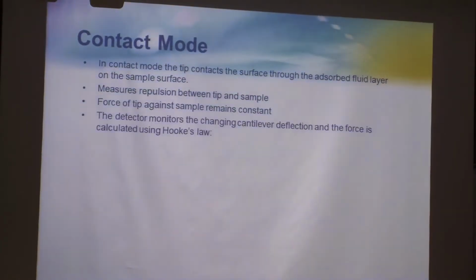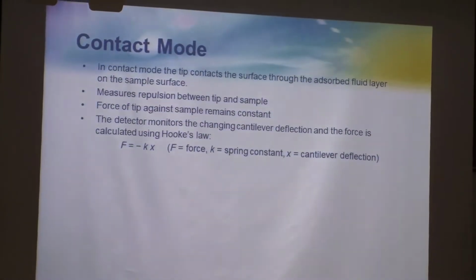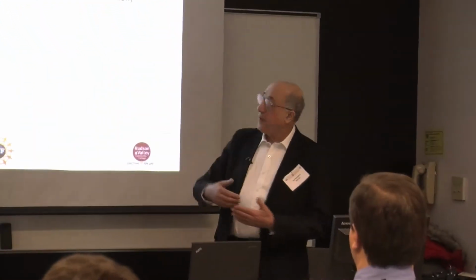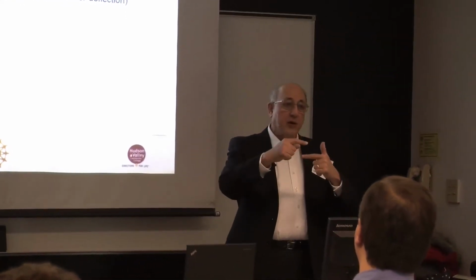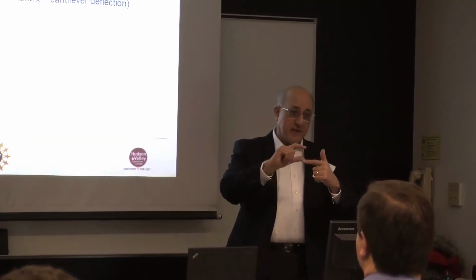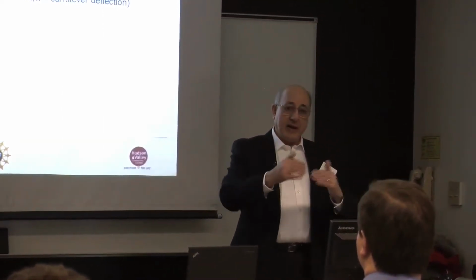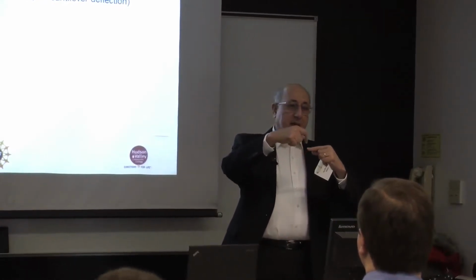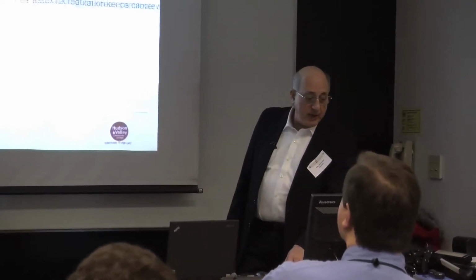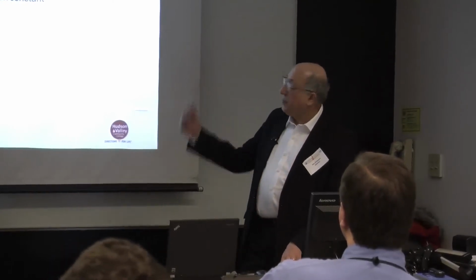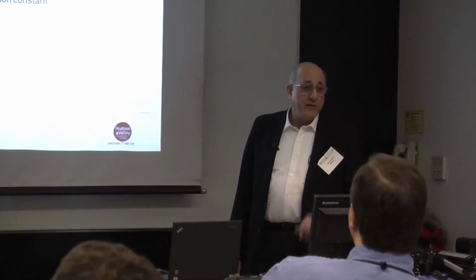Let me open this here. Are you familiar with Hooke's law in physics? This is the way that we actually measure the force. The force is nothing more than the force of interaction between two components at a distance, so it is like a spring. At the atomic level, the tip being at a particular distance means you are pushing the spring. This is the way the device calculates the force. We need feedback regulation to have a constant distance or a constant force.